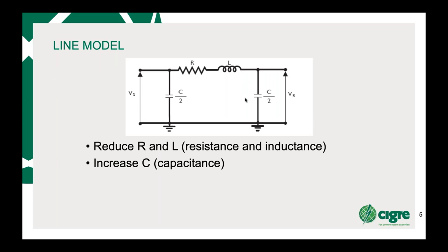Having a look at a simplified line model, in the series leg you get a resistance and inductance, and in the capacitive leg, the shunt leg, you get a capacitance to ground. So really what we're looking at when you optimize the line is to try and reduce this series leg, because this really inhibits your power flow, and increase your capacitance, which will then increase your receiving voltage. Obviously, you don't want this to be too high, because then you have to have a reactance in the network. But basically, in theory, you want to try and reduce this and increase this.